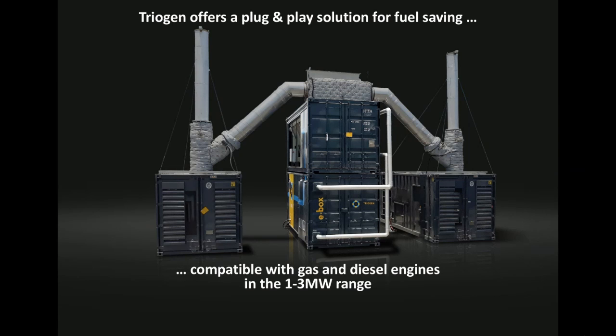What we do is offer a fuel-saving solution that you can combine with diesel gensets or gas gensets in the 1 to 3 megawatt range, roughly. In the picture here, on the left you have a genset, and on the right as well, in those containers. Those happen to be 1 megawatt gensets, so the total conventional generation installed here is around 2 megawatts. What we can do is combine the exhaust gas from those two engines. Normally it goes to the stack, the vertical pipe that goes straight up from the container, and that's it—it goes out at 500 degrees.